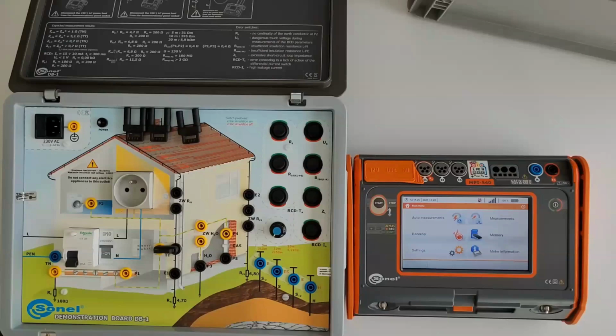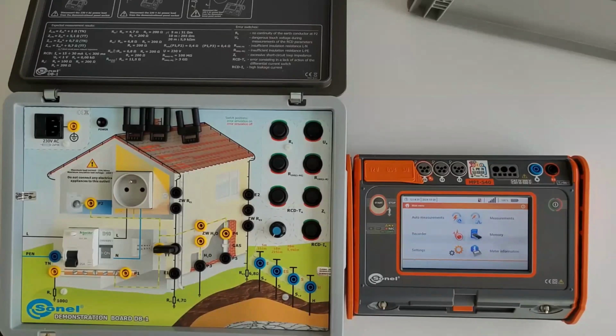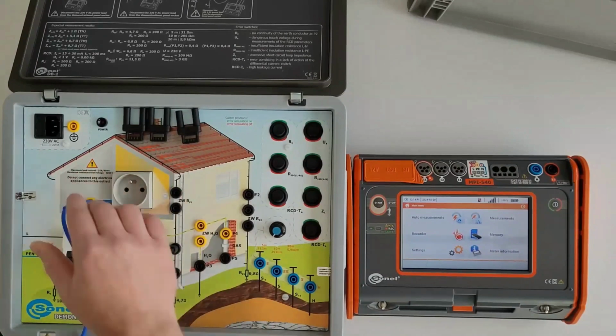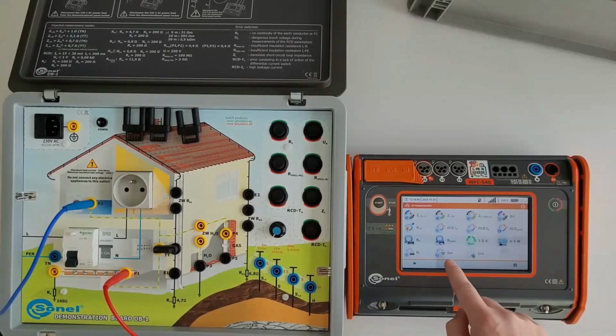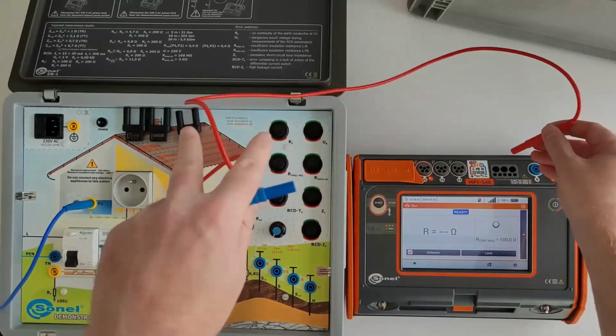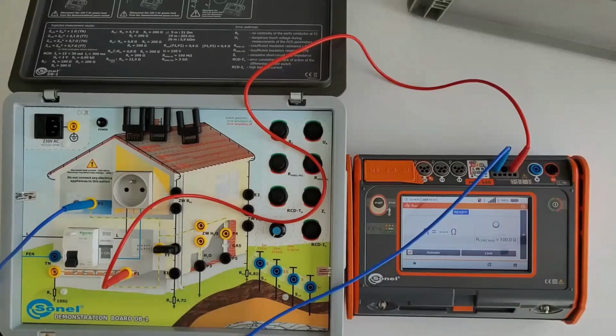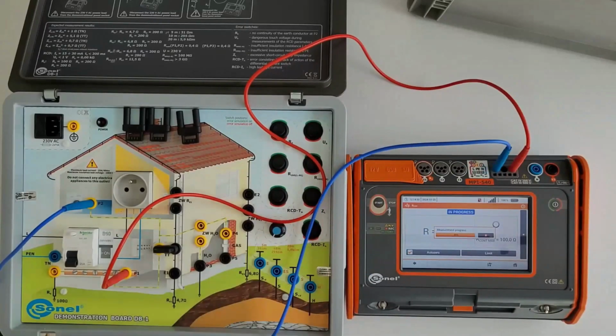I want to show you how we make the measurement of some of these parameters. The continuity of conductors and connections shall be verified by measurement of resistance on protective conductors and exposed conductive parts. We check the continuity between the main grounding bar and the housing of the current using equipment. For example, here we have a washing machine, or the ground pin of a socket. Okay, we can check. Now we can check the continuity between the main grounding bar and the housing of the current using equipment.